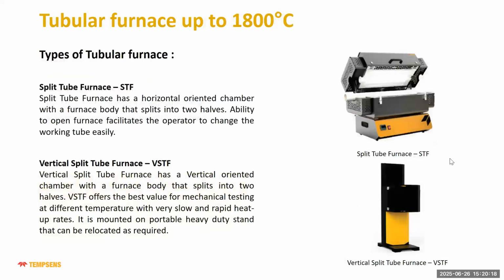Like in tubular furnace, we have different types of configuration also. So if a customer asks for a split tube furnace, we can give a split tube furnace. You can see there is a two-part split. The furnace can be split between the two tubes, and it will give you easy removal of the tube, so you can remove the tube easily whenever you want.